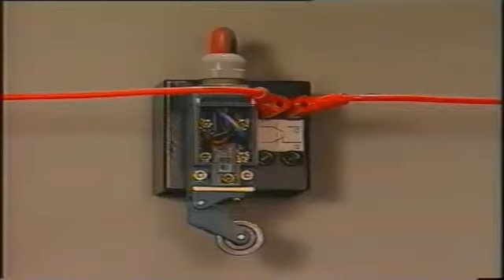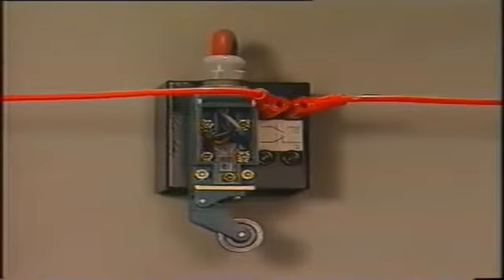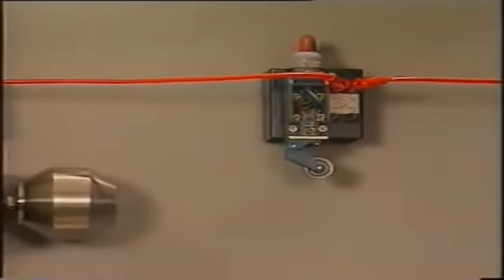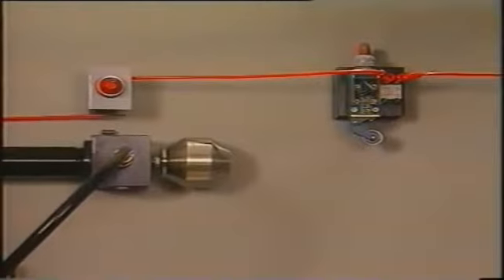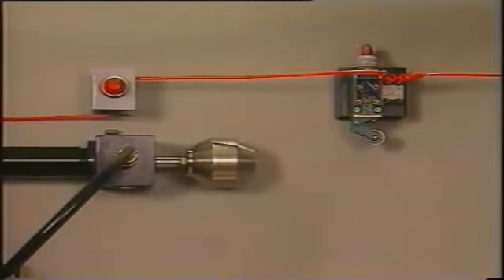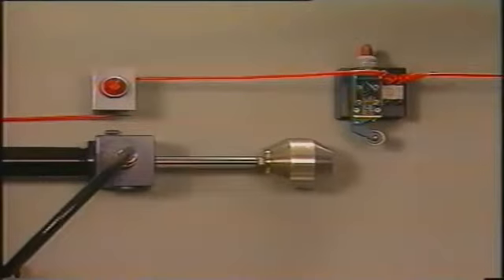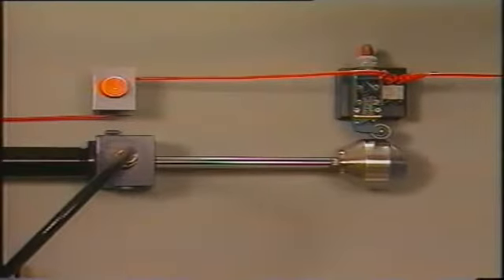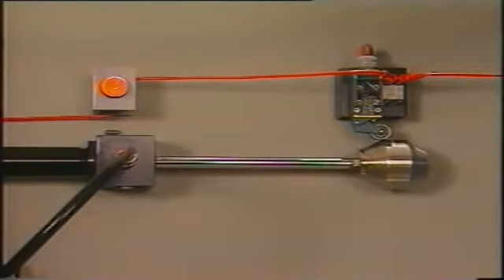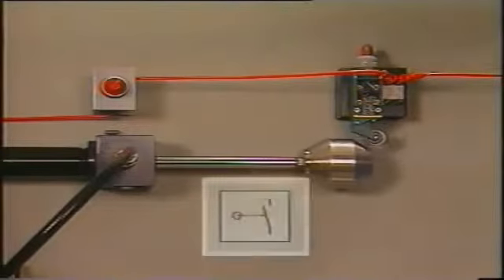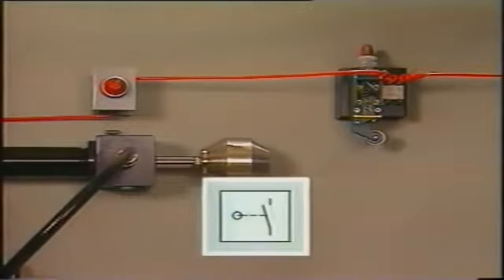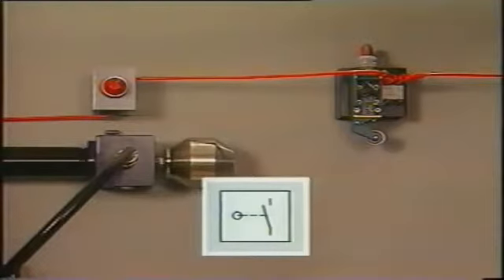This limit switch is an example for automatic mechanical signal generation. Here it is used for interrogating position. It automatically closes the circuit when the piston rod actuates the roller lever. The small circle is the symbol for mechanical actuation by means of a roller lever.